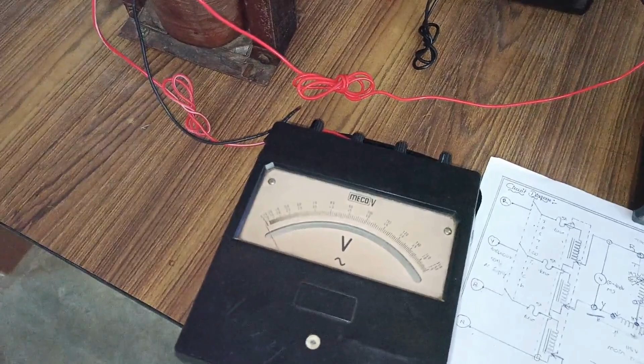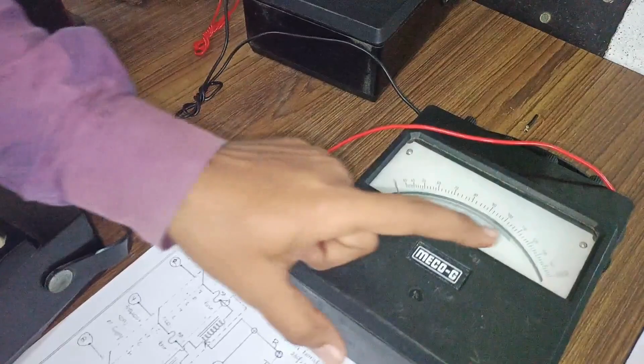This is connected to the 300 range, but the base scale is 150, so we are multiplying two times. This one is also base scale 150, connected to 300, so it is multiplied two times. That voltmeter is also connected to 150, multiplying two times. The vector sum of these two is this one, connected to 600 scale, so you multiply four times.